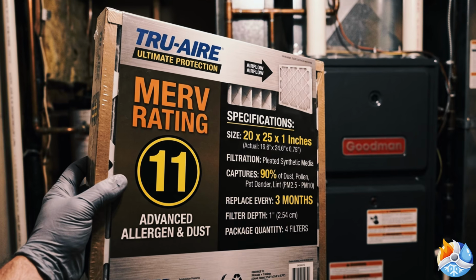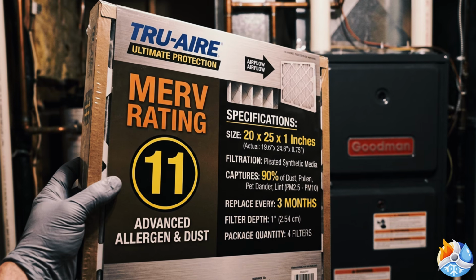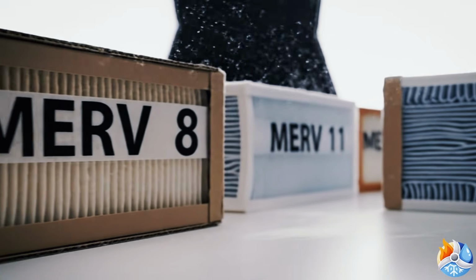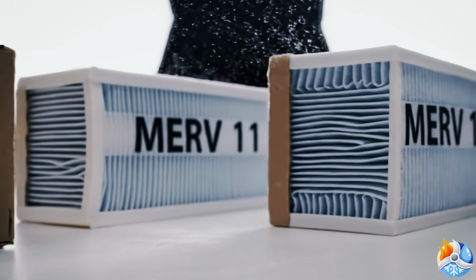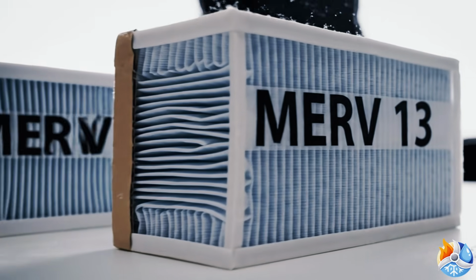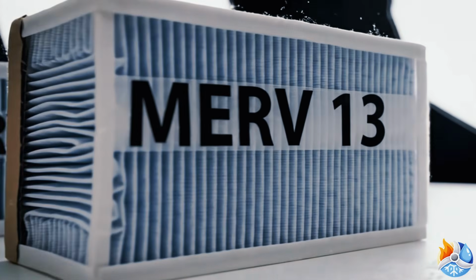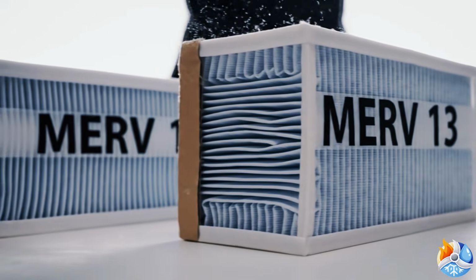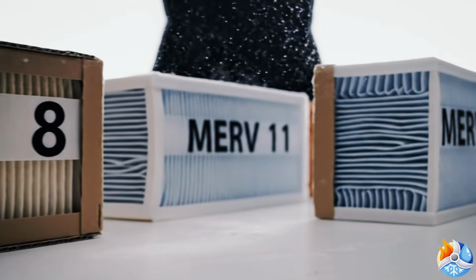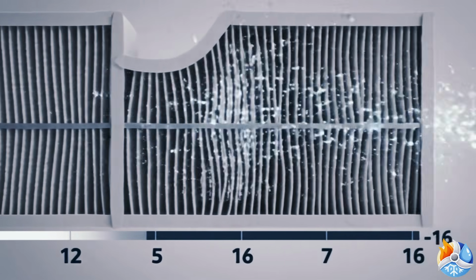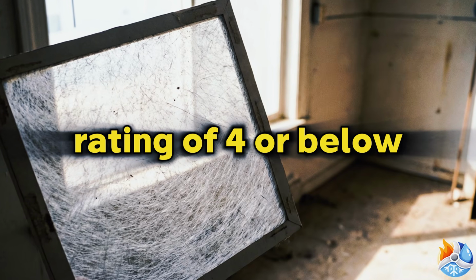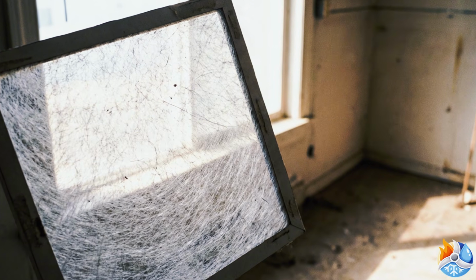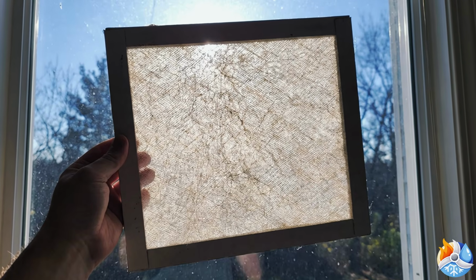Let us talk numbers, because this is where it all makes sense. There is a rating system for air filters called the minimum efficiency reporting value. Most people call it by its initials, but what it means is simple. It measures how small a particle the filter can catch. The scale runs from 1 to 16 in residential settings. Higher number means it catches smaller particles. A rating of 4 or below, that is old school fiberglass, the kind you can almost see through. Catches visible debris, not much else.